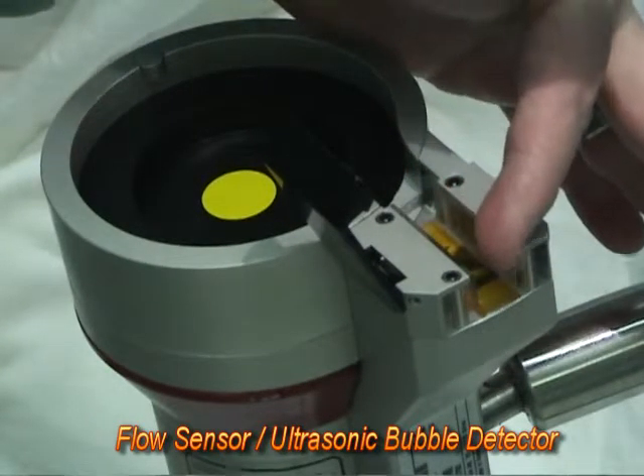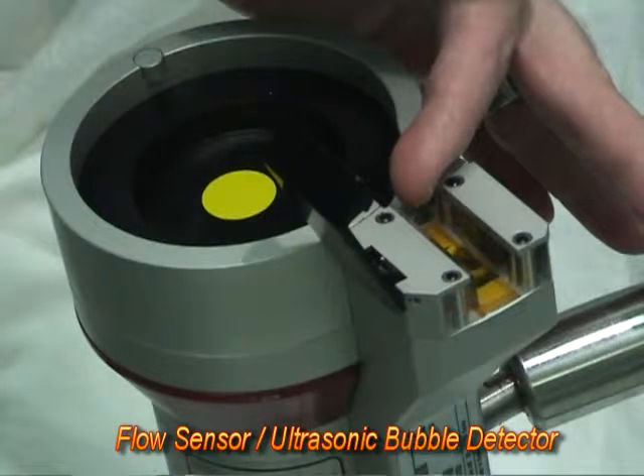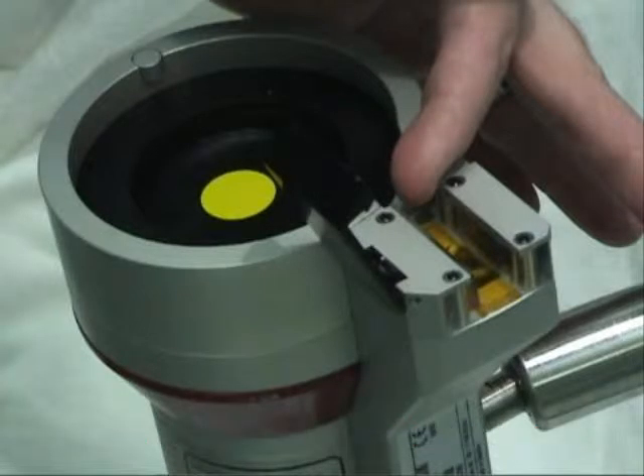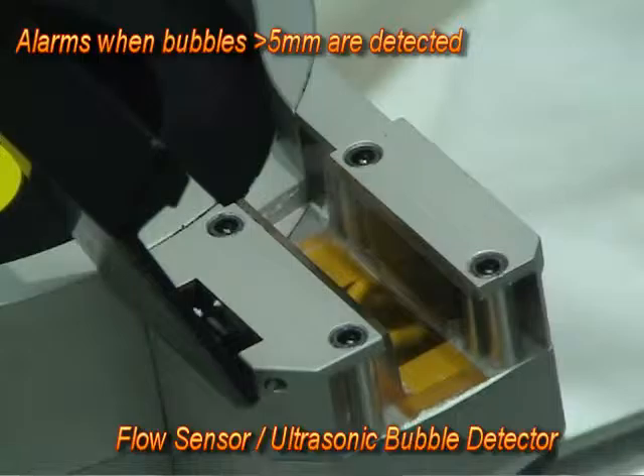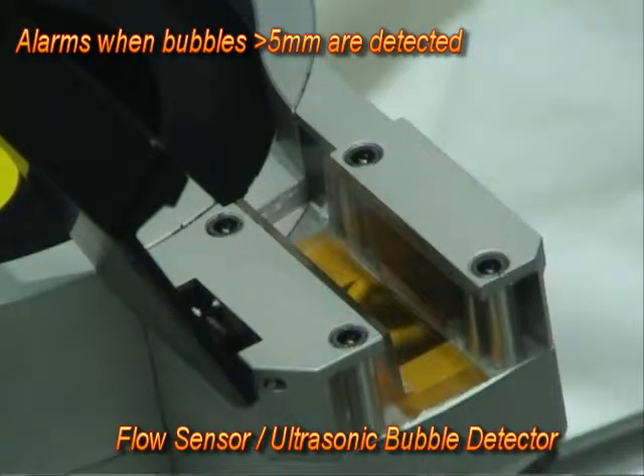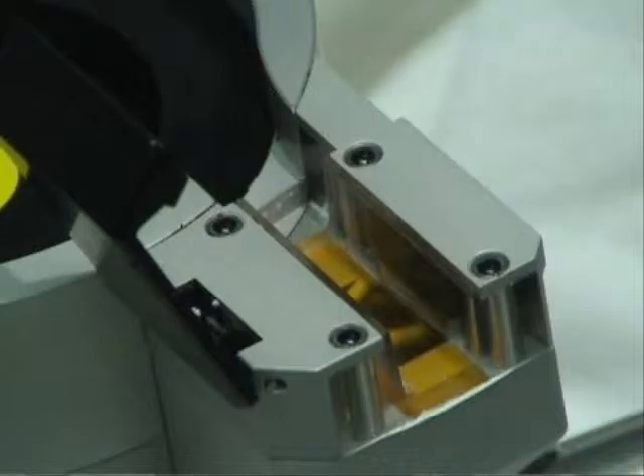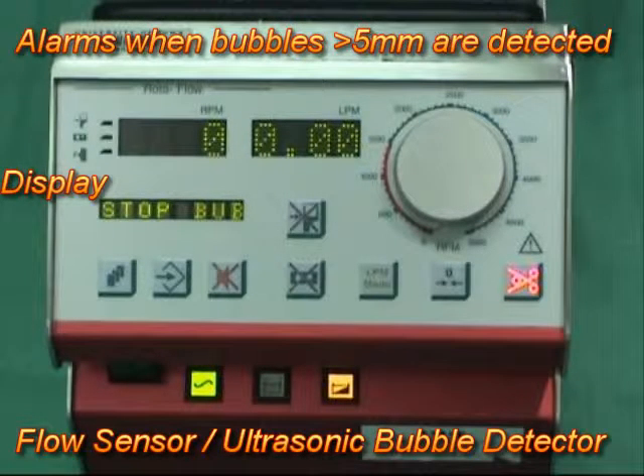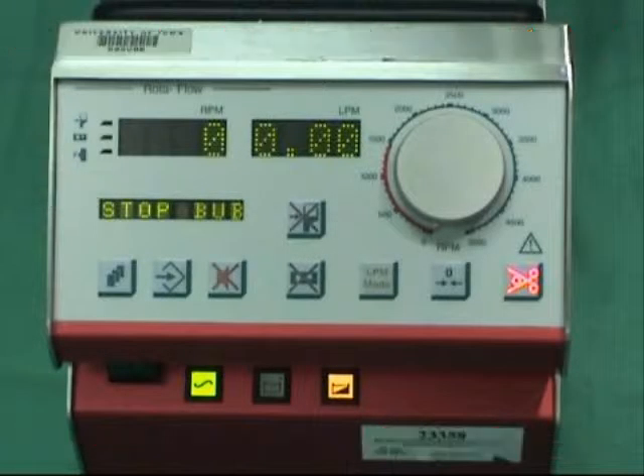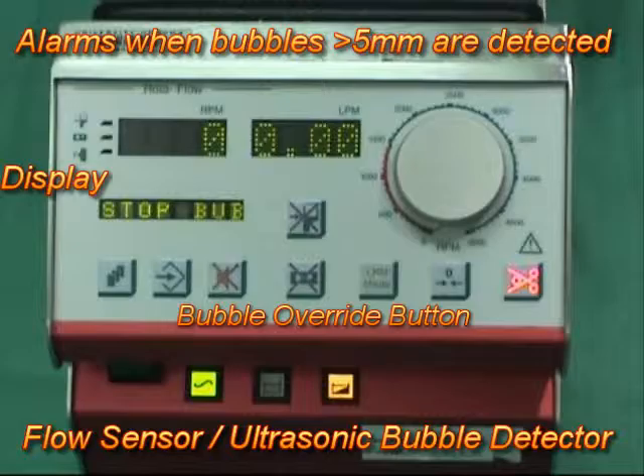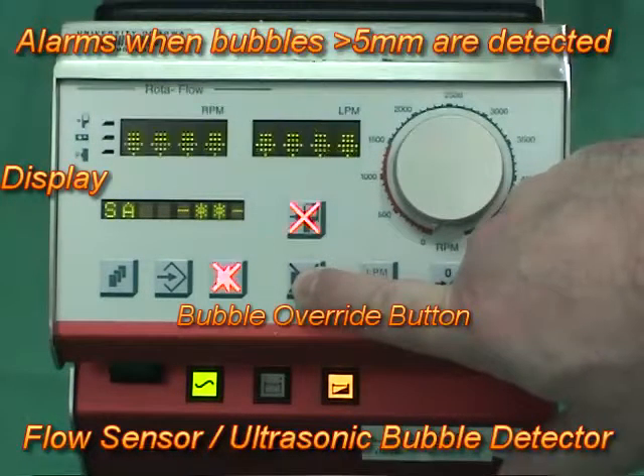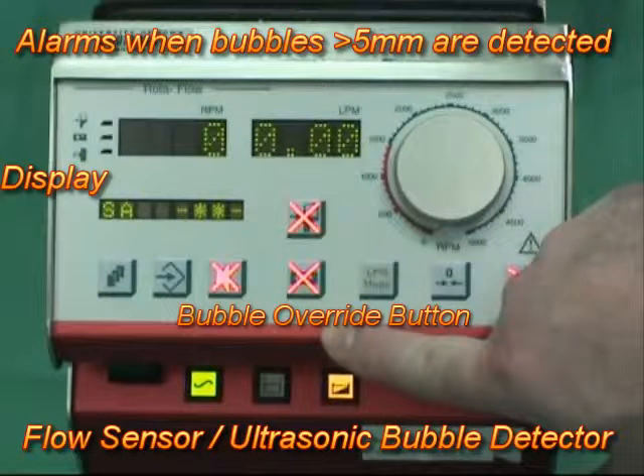The Rotoflow pump external drive has a built-in flow sensor and ultrasonic bubble sensor that alarms when bubbles larger than 5 millimeters are present. When this happens, the control panel display shows Stop Bub. The bubble override button lights and the pump stops. After correcting the actionable event, reset the bubble alarm with a single press of the bubble override button. Pressing the bubble sensor override button for 3 seconds overrides any bubble alarms and starts the pump back up, regardless of whether action to clear the line of bubbles is taken.